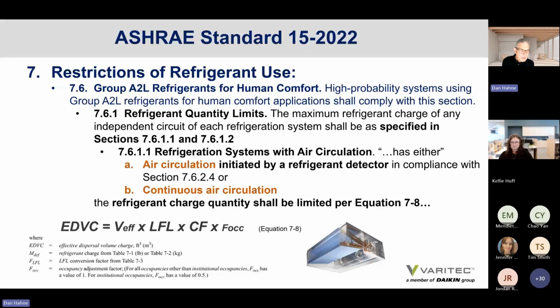I'm sorry, can you repeat that? Like for R410A, you have to use the RCL calculation for Standard 15. For A2Ls, it moves you to this new equation based off of LFL. Does that mean that we can avoid the RCL calc for A2L refrigerants so long as we have systems with air circulation? In my going through the standard, I did not see any language that would support that idea. So my question really is, when you're running through some example calcs, is the RCL still your driving limiting factor, just because the volume went down so much per 1,000 feet?